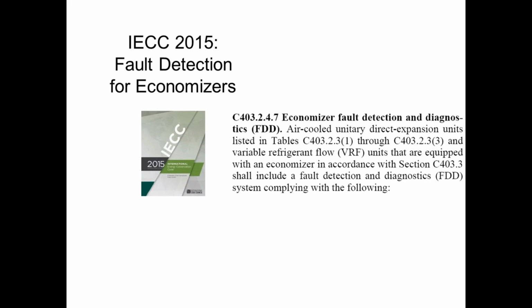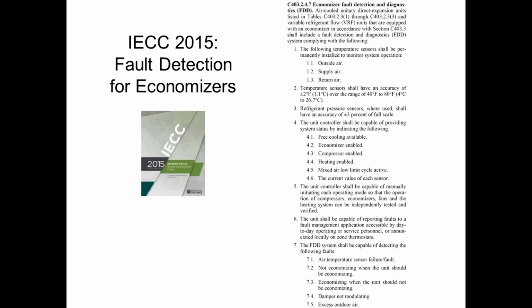Title 24 in California uses the same acronym as the code here, and all the rooftop manufacturers know exactly what FDD means. And most of the thermostat manufacturers and economizer controller guys know what it is as well. So it applies to lots of types of systems, including packaged rooftop units. Here's all the requirements, which I won't read you in gory detail, but the economizer has to be able to detect certain problems if temperatures are out of whack, if the damper's not opening when it's supposed to, if it's not closing when it's supposed to, if it won't modulate, if you have too much outside air, if the sensors are messed up, whatever the case may be.